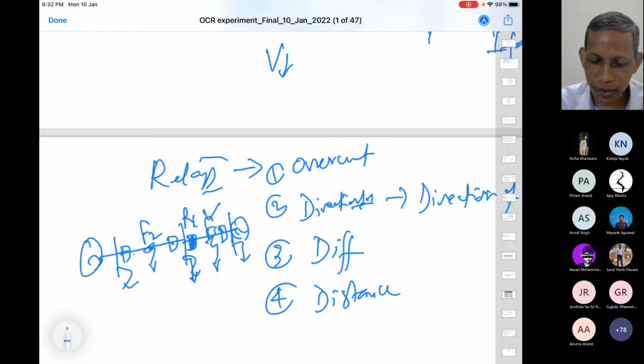Current can be for both sides, so F1 and F2 currents can be substantially high. So overcurrent will not be able to discriminate that. So we require discrimination of whether the fault is on the right side or the left side, to operate the proper circuit breaker, this breaker or this breaker. In that case, let us think the relay R1 has to be able to discriminate whether the fault is on this side or this side. If it is on this side, it will operate this breaker, or it remains silent. For the other breaker, there will be another relay.